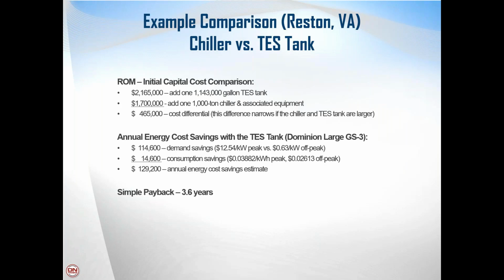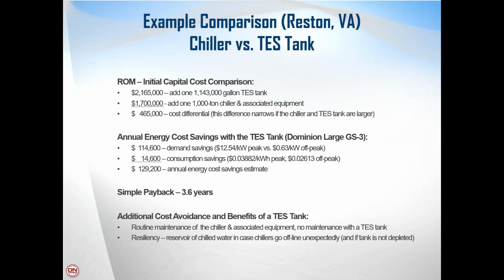And in just a very high level, simple payback, that's about a 3.6-year payback. Even though the tank is a little bit more expensive, in less than 4 years, it'll pay for itself and continue to pay for itself for as long as they continue to use that tank. With the additional benefits of lower maintenance costs, because now there's almost no maintenance with the tank, but there would have been a lot of maintenance with that additional chiller and cooling tower. Plus, they have the resiliency of all of this large reservoir of cold water on this campus for either backing up their central plant system or helping put out a fire.